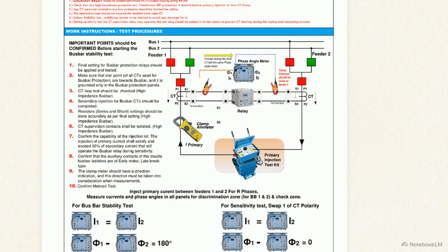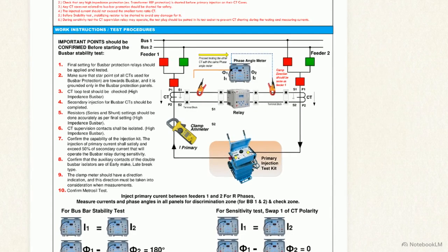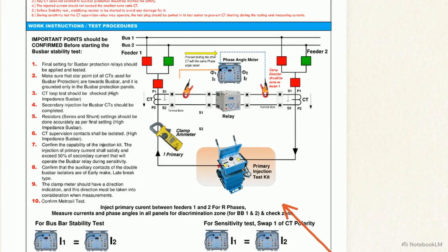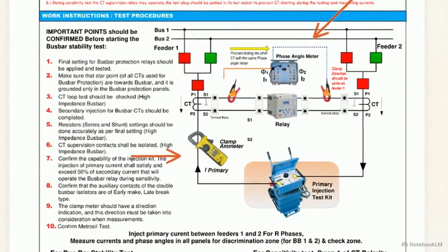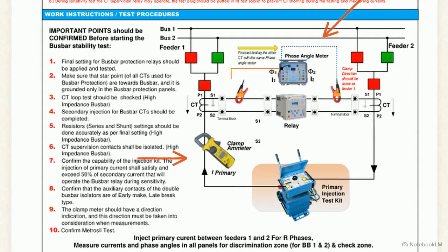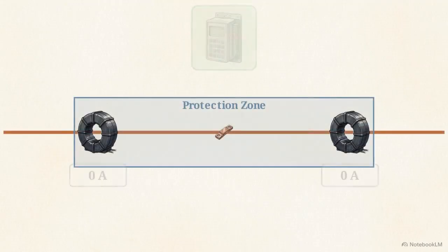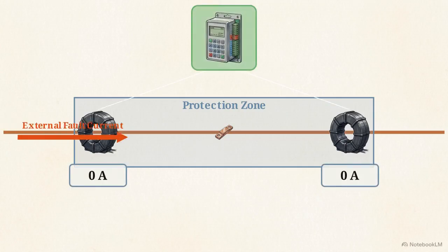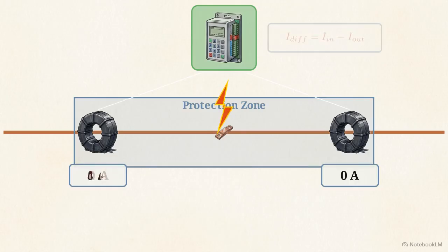Busbars and reactors require both stability and sensitivity tests. As shown in this primary injection diagram, the team must push massive primary test currents through the actual high-voltage conductors, using phase angle meters and clamp meters to verify the full physical circuit. The expected behavior is twofold. During the external stability test, the relay must ignore a massive fault current passing through the zone. During the internal sensitivity test, an injected fault inside the zone must yield an immediate trip.